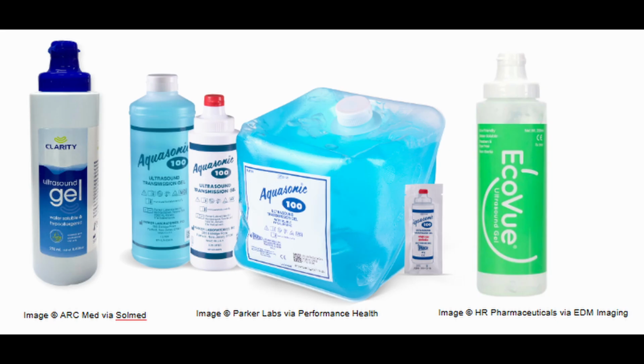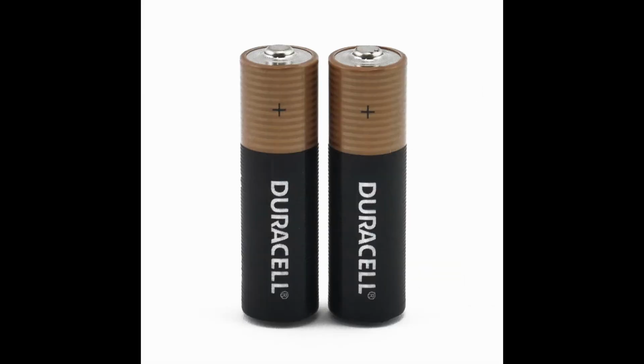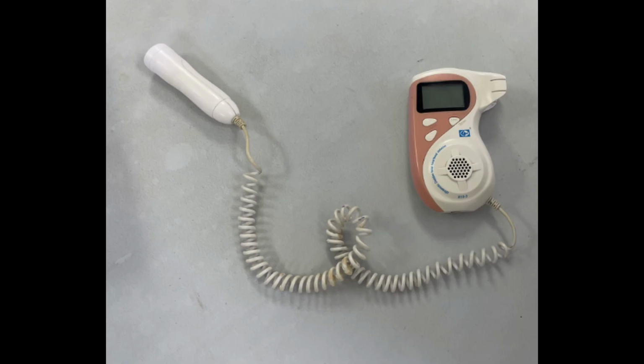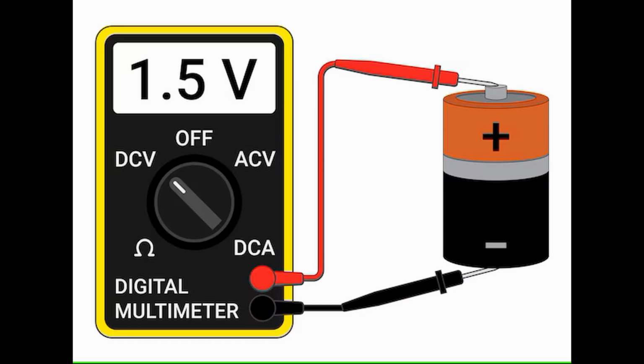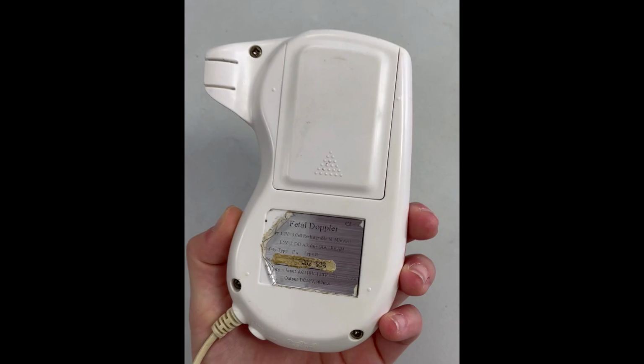The consumables for this device include ultrasound gel, which enhances signal transmission between the probe and the skin, and batteries, which provide power for portable operation. As a battery-operated device, it's important to maintain a healthy battery level and regularly change out batteries to avoid failure. Fresh AA or AAA batteries should each supply a 1.5 volt potential. You can check the voltage supplied by batteries by removing them from the device and using a multimeter. You can also check the battery type from the manual for the device or by opening up the back panel of the device to view the batteries.